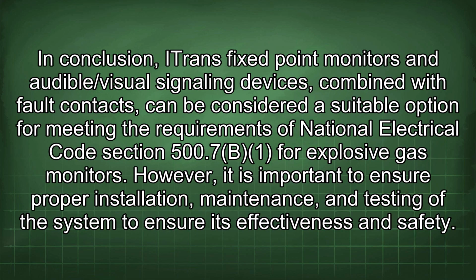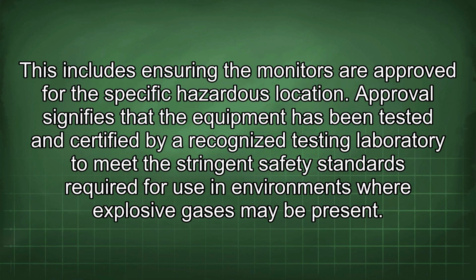In conclusion, ITrans fixed-point monitors and audible/visual signaling devices combined with fault contacts can be considered a suitable option for meeting the requirements of National Electrical Code Section 500.7(B)(1) for explosive gas monitors. However, it is important to ensure proper installation, maintenance, and testing of the system to ensure its effectiveness and safety. This includes ensuring the monitors are approved for the specific hazardous location. Approval signifies that the equipment has been tested and certified by a recognized testing laboratory to meet the stringent safety standards required for use in environments where explosive gases may be present.